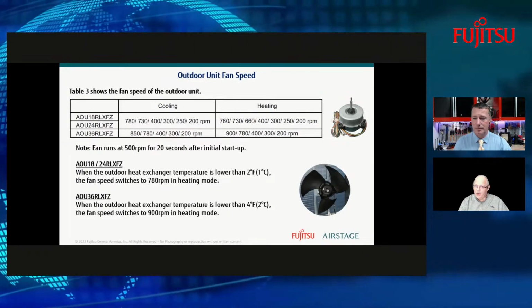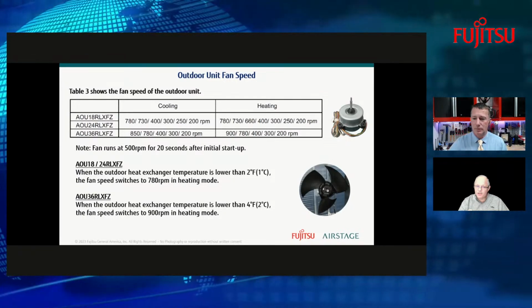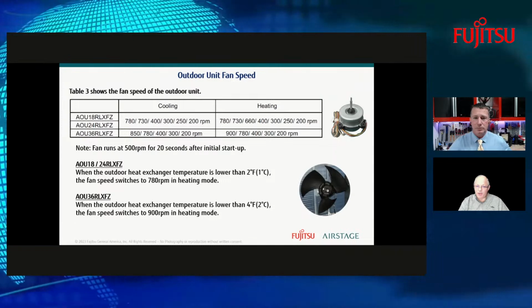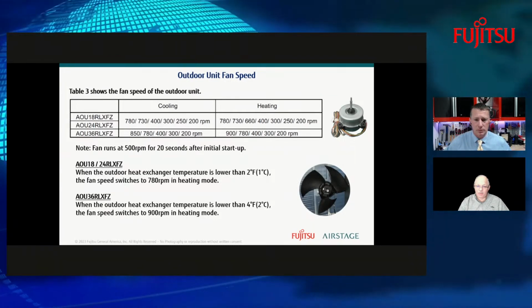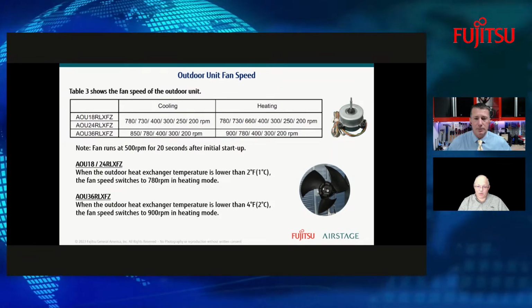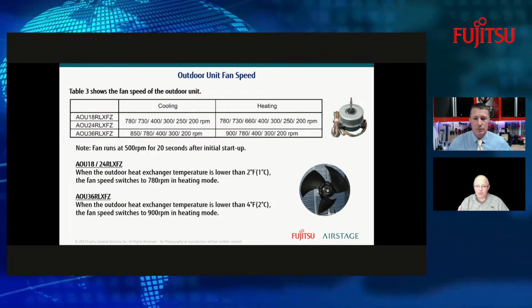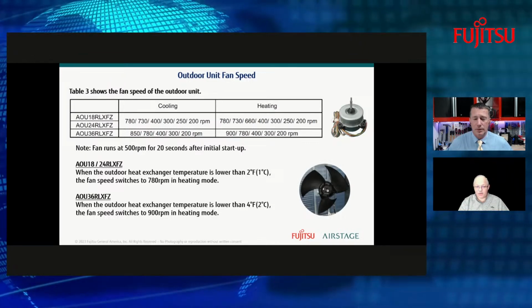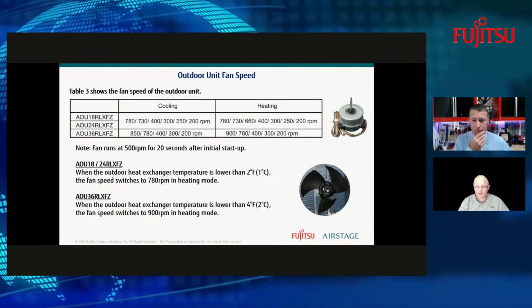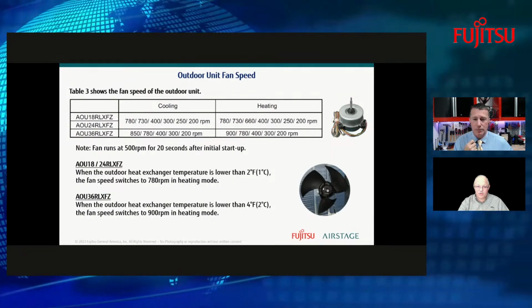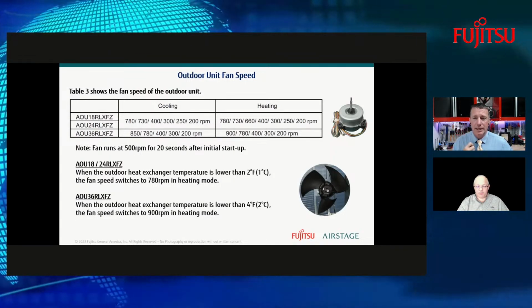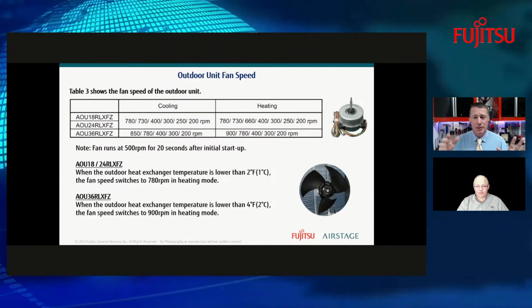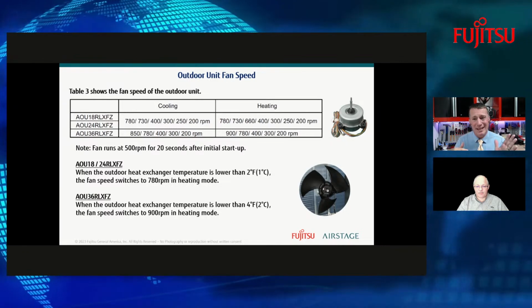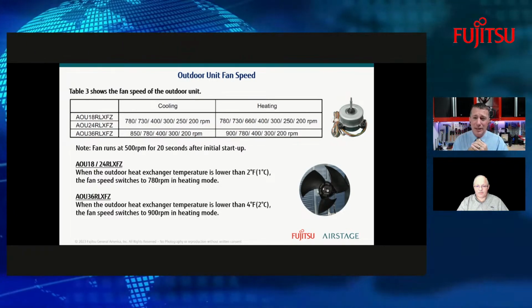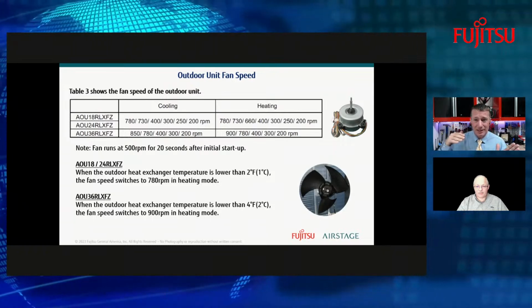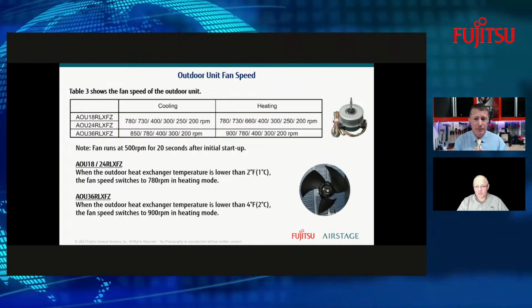So that's why it's important to have a good, clean outdoor coil all the time. Critical on these systems. Yeah, and as you look at the different models here, you can see that they're designed to run at varying RPM. So depending on where the system is at, both temperature-wise outside and inside, depending on what the load is, will depend upon how far up the modulation it's going to go. So it's nice to understand what makes these fan motors increase in speed along with the compressor. Now, I noticed with the compressor, especially on that smaller unit, it goes from 20 RPS up to 100 RPS. So we're looking at a unit that can go from 20% capacity up to 100% capacity, approximately? Yeah, somewhere in that range.